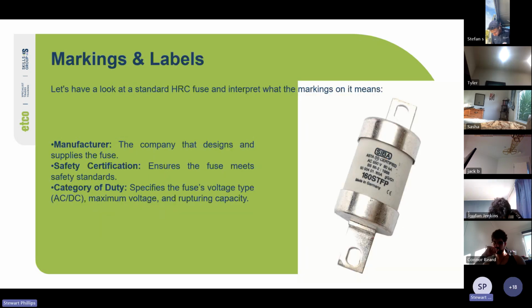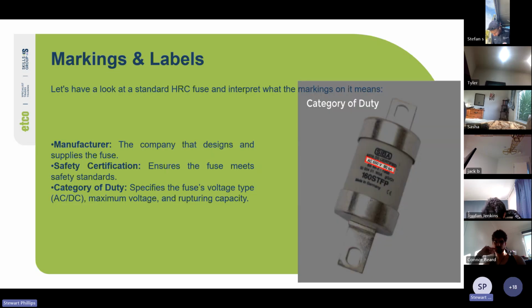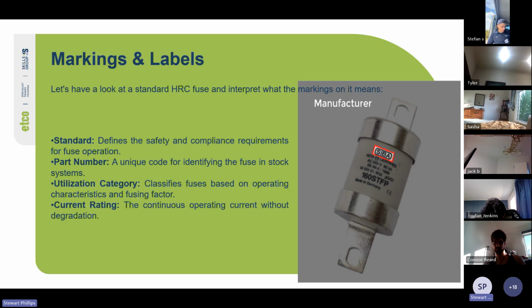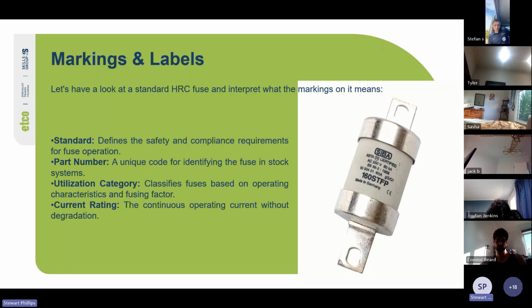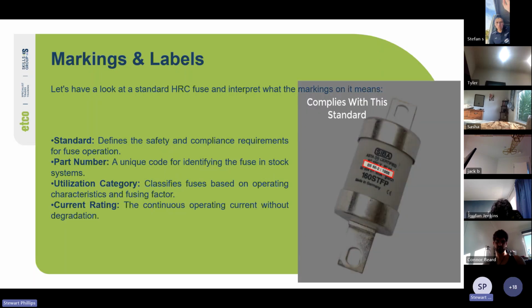Cool. So you've got your markings and labels. A standard HRC fuse has the manufacturer, the company that supplies the fuse, a safety certification, which ensures the fuse meets safety standards, and a category of duty, which specifies the fuse's voltage type, AC or DC, the maximum voltage, and the rupturing capacity. It has a standard written on it, which defines the safety and compliance requirements. It's got a part number, a unique code for identifying the fuse in stock systems. So you can call up, give them the part number, and they can find the fuse. And if they don't have it, they can offer you a suitable replacement. A utilization category classifies fuses based on operating characteristics and fusing factor. And current rating is the continuous operating current without degradation.